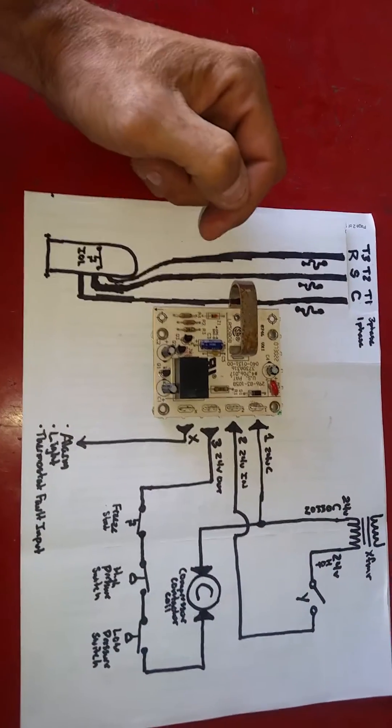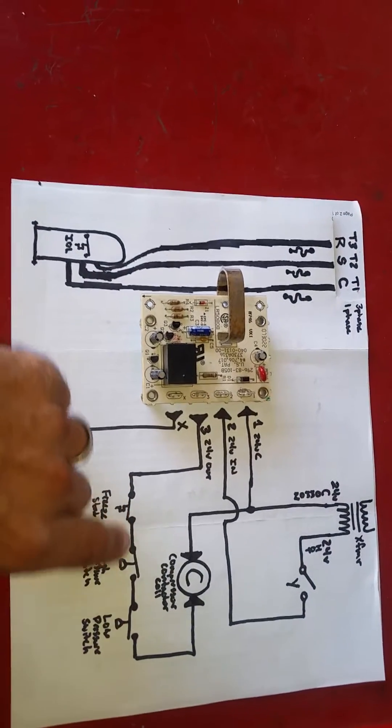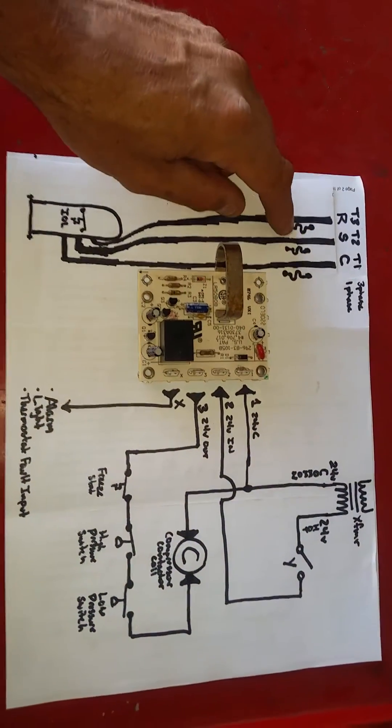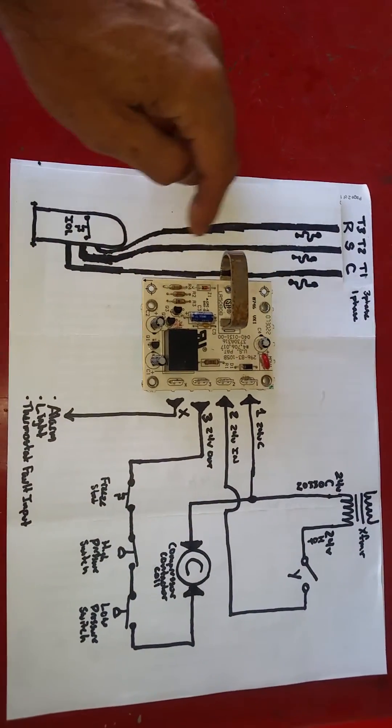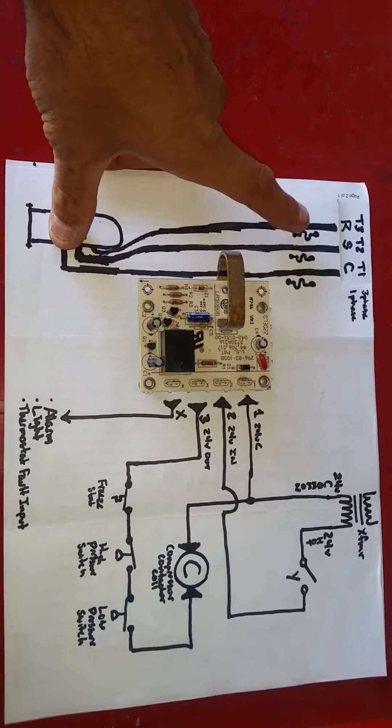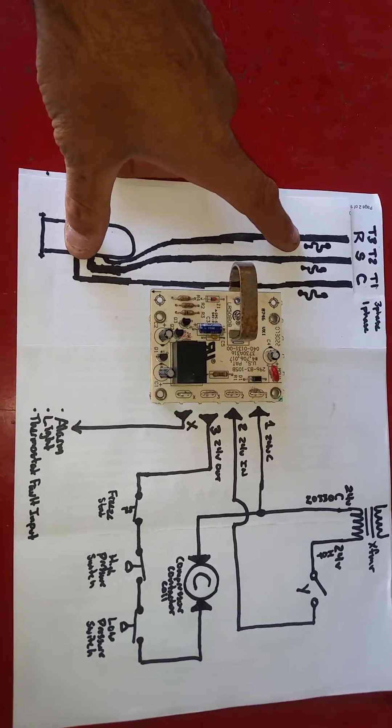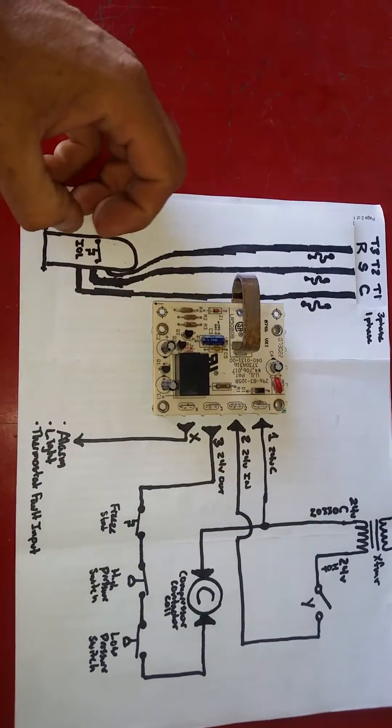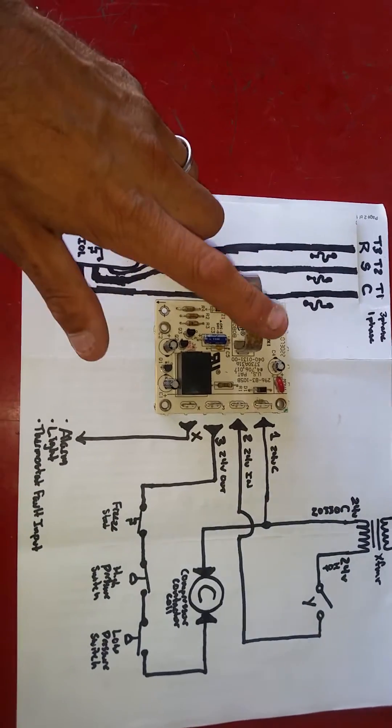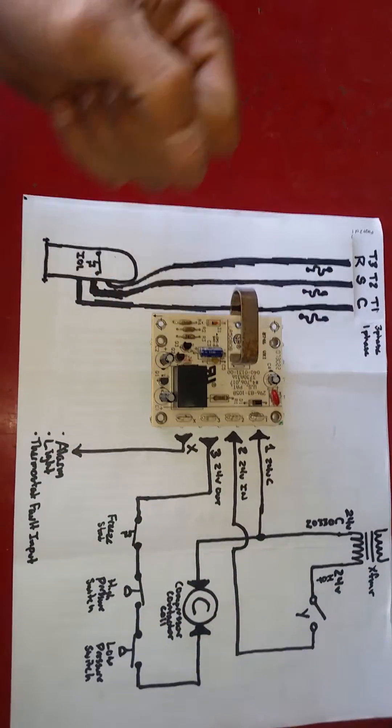We also got to realize that the safety switches aren't the only culprits that may open on this type of circuit. I drew in some fuses here. Our line voltage or our load voltage to our compressor may run through a fuse block. If one of these fuses open on a three-phase, of course, we're going to basically have an open compressor. A compressor shuts down. We do no longer have current that our sensor can monitor and our system opens.